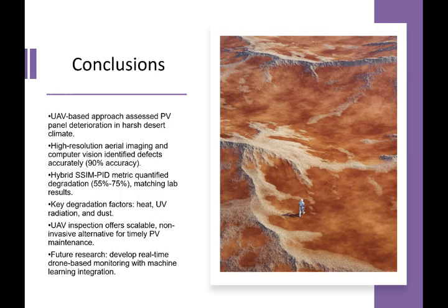So the conclusion: the UAV-based approach assessed PV panels in a harsh climate, and high resolution aerial imaging and computer vision identified the defects with accuracy of 90%. Sorry, I'm running out of time, so I have to make it a bit quick. The hybrid SSIM PID metric quantifies the degradation at 55% to 75%.